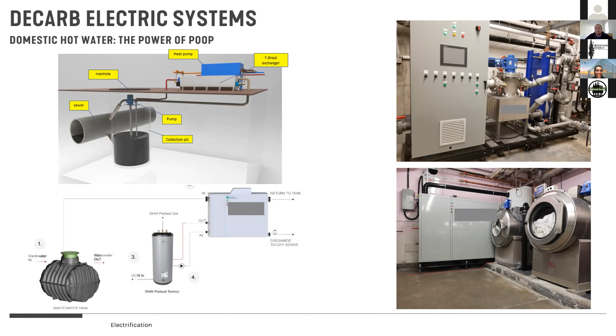And a big reason for that is the effluent leaving the building is at an extremely consistent temperature. If you think about it, when I need hot water in a residential building, it's likely because I'm using a lot of shower water. Well, that wastewater coming out of the shower is a great source to steal heat from. And so instead of trying to steal heat from 0 degree temperature outside, I can steal it from a 70 degree, 75 degree interior or effluent temperature leaving the building. So instead of a COP of 1, I can hover around a 4, 4.2.